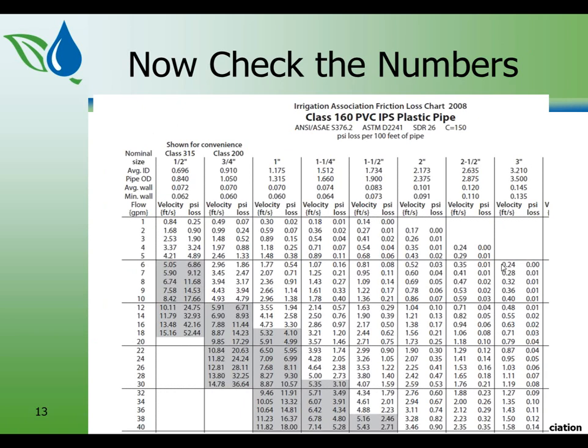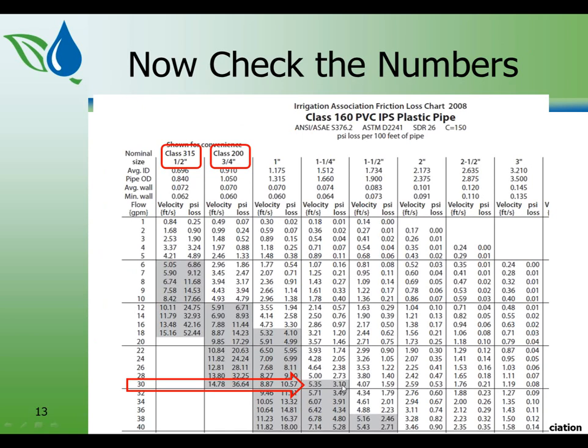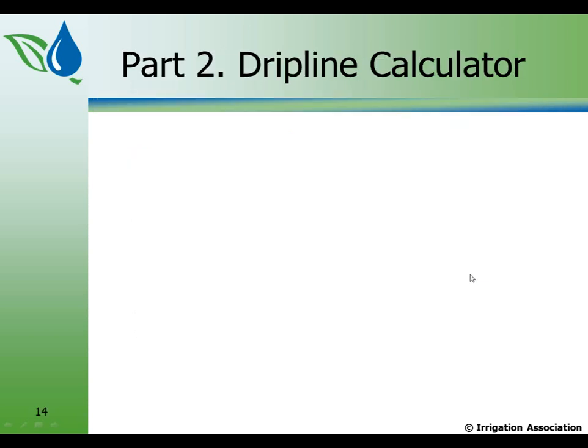So we're looking at class 160 PVC. And notice here that in the chart, we show the three quarter, but it's class 200. And it's shown for convenience. And in half inch, it's class 315. Same thing, shown for convenience. When we look at that one leg we were looking at, and I had it mistyped as 30 gallons a minute, which should have been 32, we've got 5.35 and 3.1. 5.35 is the velocity, the same number we got. And the friction loss was .93. Now this, that was 30 feet out of 100. This is loss for 100 feet. So .3 times 3.1 gives you .93. And that's the answer that we got in the spreadsheet. That's sometimes worthwhile to check and see what you really get. Now, if we'd done that right, we'd have been down here on the 32 line, which is 5.71 and 3.49.